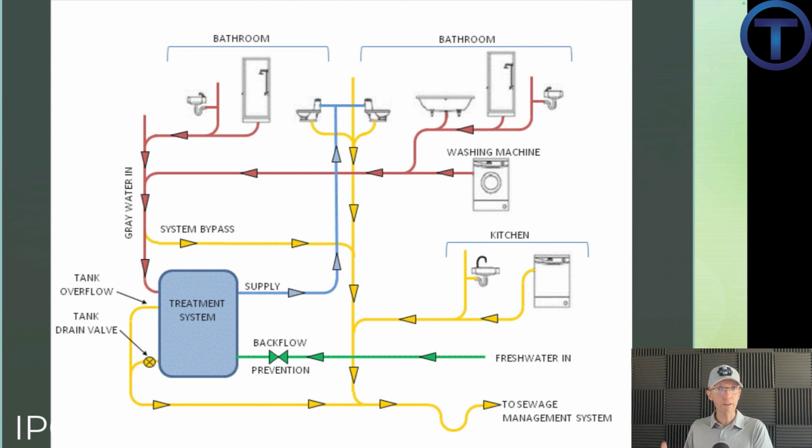If I was going to do a bathroom group and save some venting, do a wet vent, well, now I've separated the toilets, so they have to have separate venting. And it gets more involved with piping. You can see that right away. Look at potable. The potable system is now going to have separate piping going to all the toilets. So normally I just run my cold water and branch off here and there and get her done. Now I've got another line running through the whole house just to go to the toilets. So you can see there on both the waste and the water side, we've got more labor, more materials happening to get this system in.